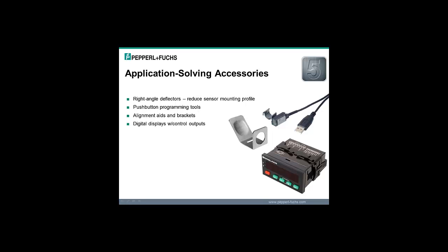Okay, this is going now to section 5 of our basic training for ultrasonics, and this is a quick look at application solving accessories. So we have right angle deflectors that will reduce the sensor mounting profile. So you can see on, I guess, middle left, if you thread a sensor through the through hole there and mount it, the sensor sound can go from the transducer and bank off that 45-degree angle and then go out to look at a target. So you can get kind of a periscope effect with your ultrasonic sensor.